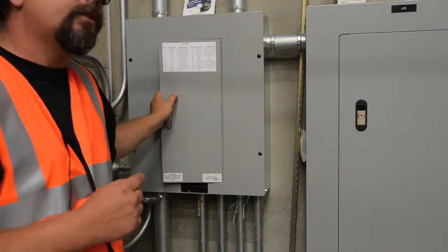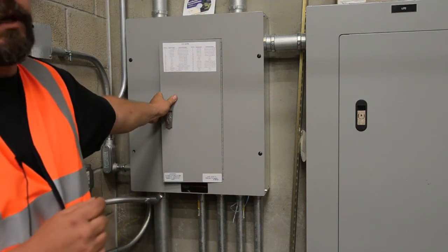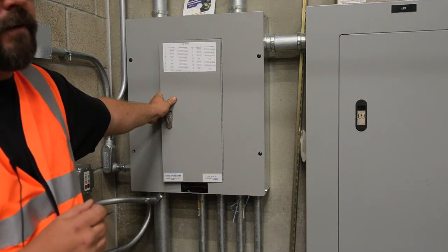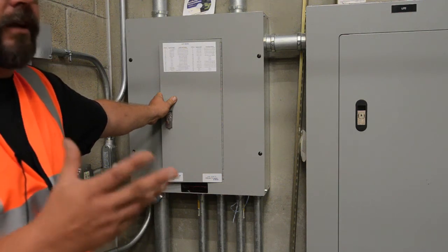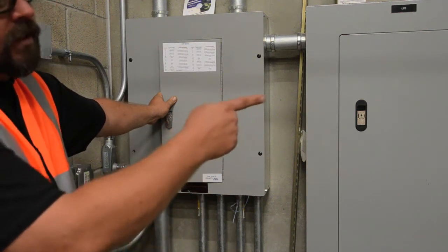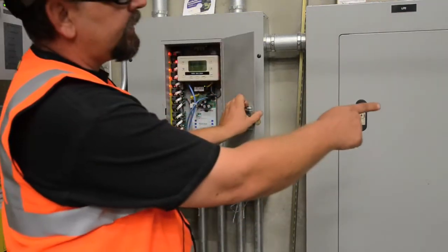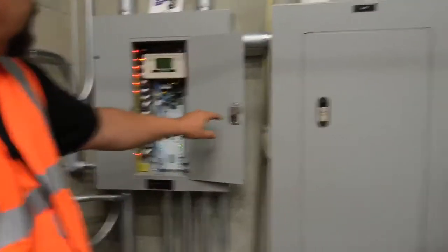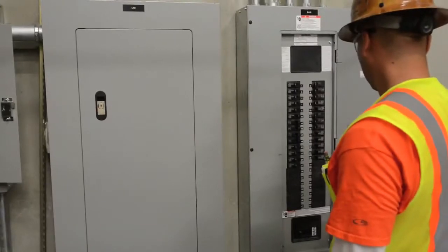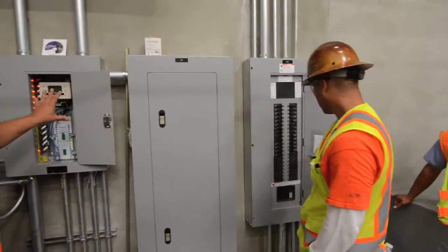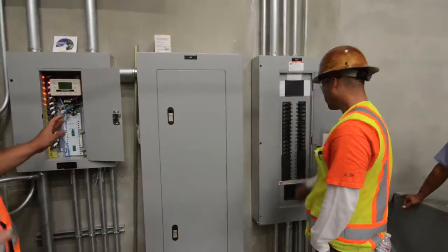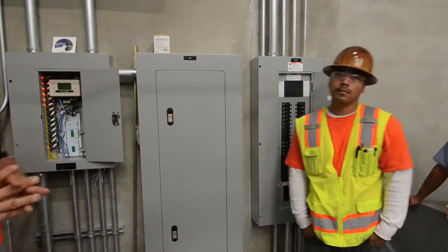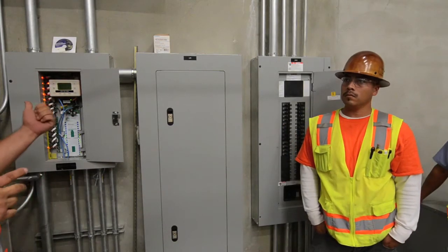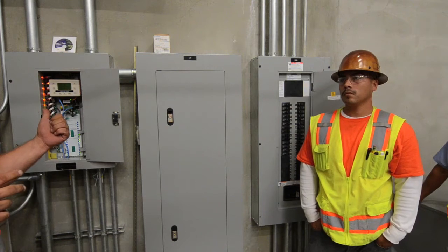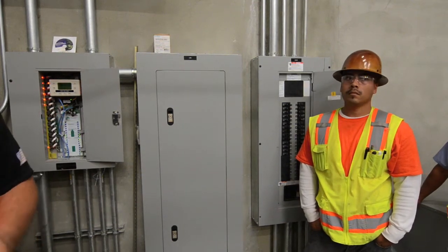So these relays are normally closed relays in the de-energized position. So if, let's say, somebody accidentally turns off your circuit — go ahead and open up ELV2, Fred — let's say somebody turns off the circuit that feeds this panel, what will happen is all relays will fail to the closed position.